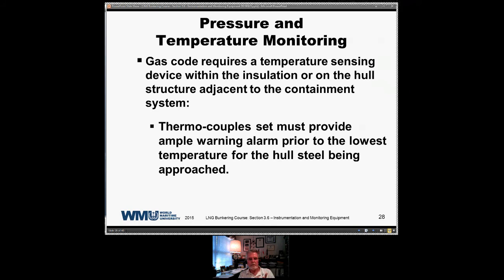Any indication that the temperature drops dramatically, you're going to have a transitional temperature change, obviously, from the tank skin as you work your way through the insulation. But if you get a sudden drop, let's say outside the second barrier, the temperature is going to be pretty near ambient, and all of a sudden that temperature starts to drop, you have a leak of some type. So temperature is an excellent indicator of any potential leak in your containment system. Again, the number of leaks that we have seen over the years is absolutely minimal. But these things do show up, and they show up very, very quickly.